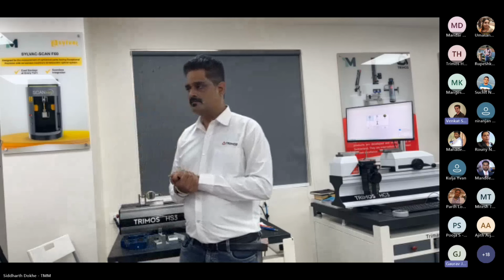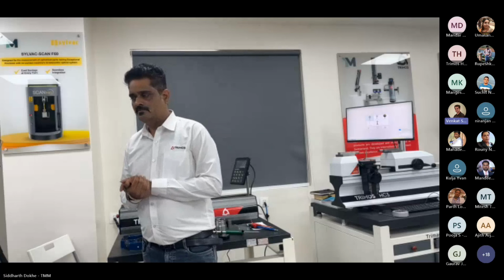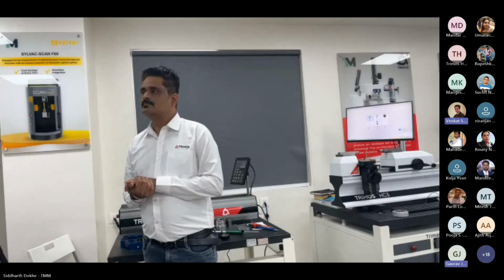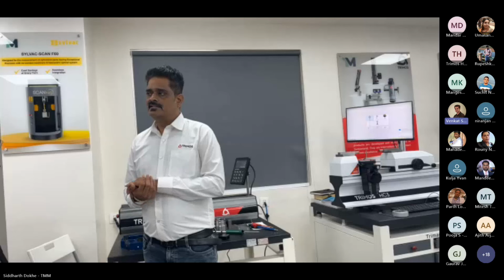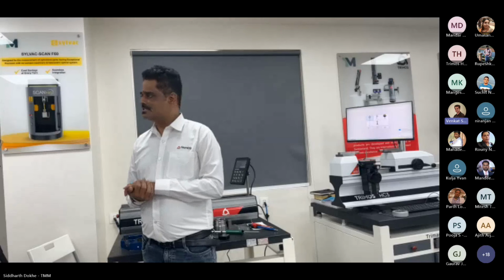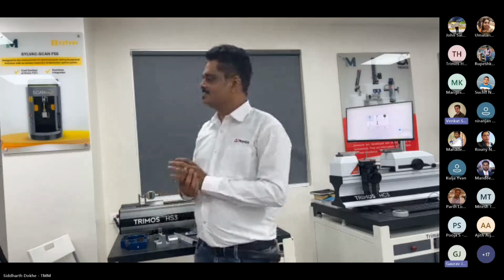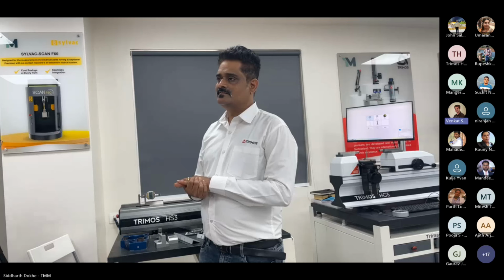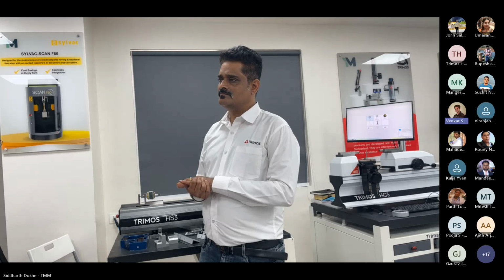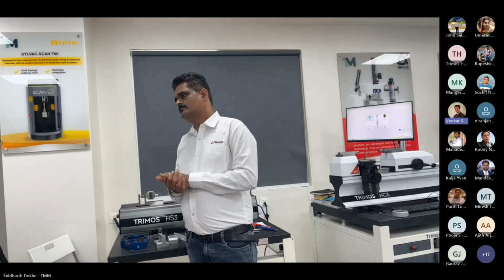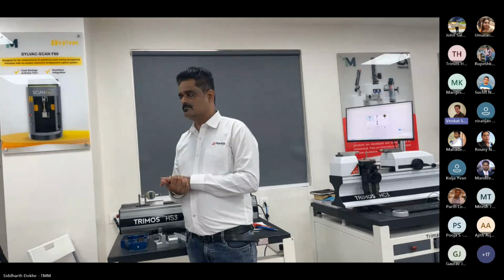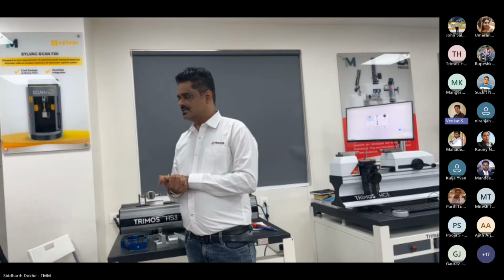I was just coming to add that the process of calibration is also completely eliminated for all of those setting rings. Many companies have to send their setting rings outside for calibration, and during those 2, 3 weeks that it takes to calibrate those gauges, they still need to run the shop. So they maintain backup rings or plugs, etc. But in this case, the calibration is done completely in-house. So even for the instrument, there is no downtime, no sending and waiting for gauges, and that additional investment is also saved.